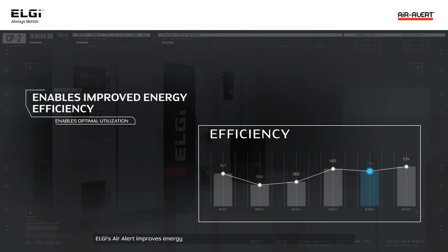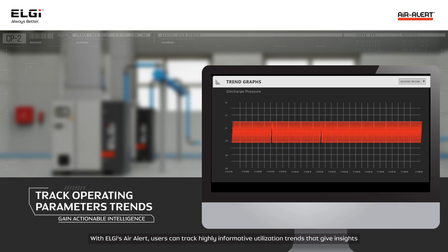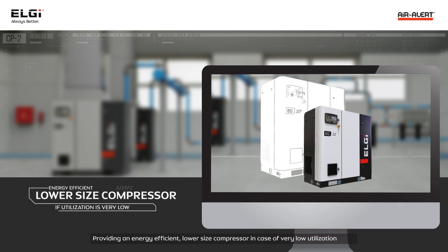ELGi's Air Alert improves energy efficiency on a large scale where utilization is not optimal. Users can track highly informative utilization trends that give insights into utilization, empowering them to take corrective actions such as: operating pressure band optimization based on utilization rate; replacing an existing fixed speed unit with a variable speed VFD unit or adding a retrofit VFD; and providing an energy efficient, lower size compressor in case of very low utilization rate.